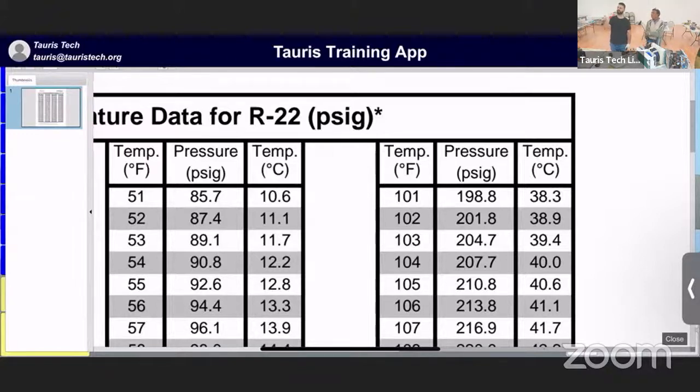Okay, so once you get the graph and you look, anything above that number becomes superheated. Usually we want to stay within a certain range of superheat, about 10 degrees. In your evaporator, you don't want 50 degrees of superheat, because you have to understand something.